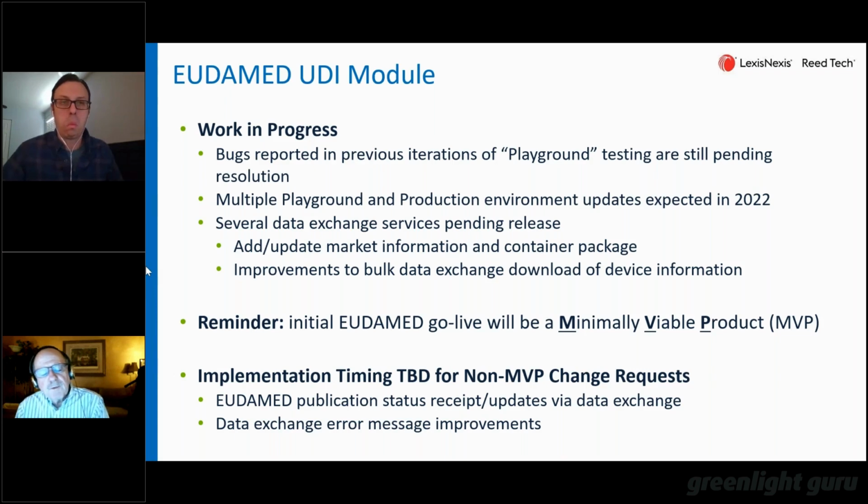So John, while you were talking about that data exchange service, one question came in, probably can answer it right off the top of your head. Is there an option to submit data as a spreadsheet with the content captured in a spreadsheet and then upload it through the user interface? No, the only EUDAMED user interface file format that they're accepting right now is XML. So it's essentially the same XML file built according to their schema, that instead of using an AS4 gateway to submit to them through the access point, you could upload that file.